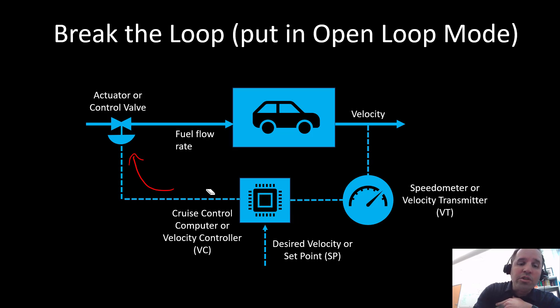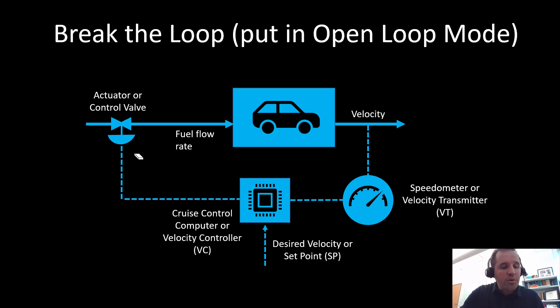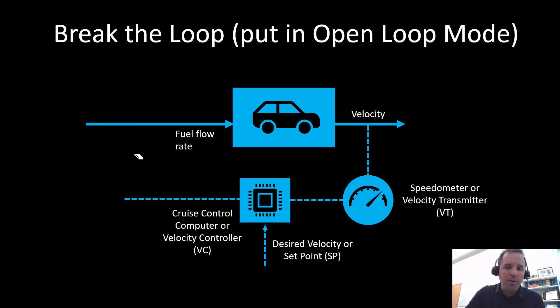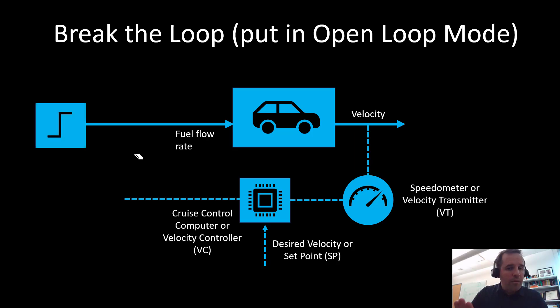To tune a controller, we are trying to obtain values for our proportional and integral controller gains. The first step is to break the loop by disconnecting the controller from the fuel flow rate variable. This is equivalent to driving down the highway and suddenly making a step change in pedal position.